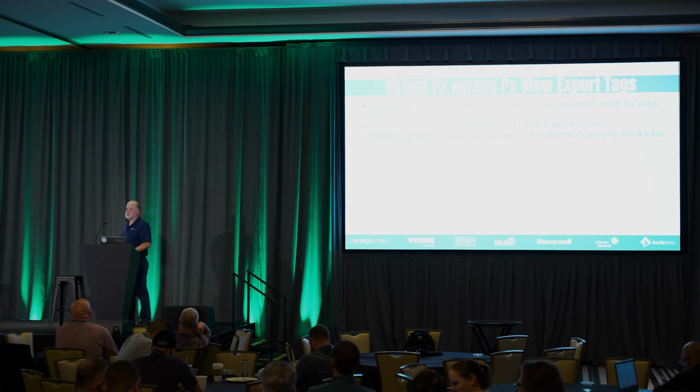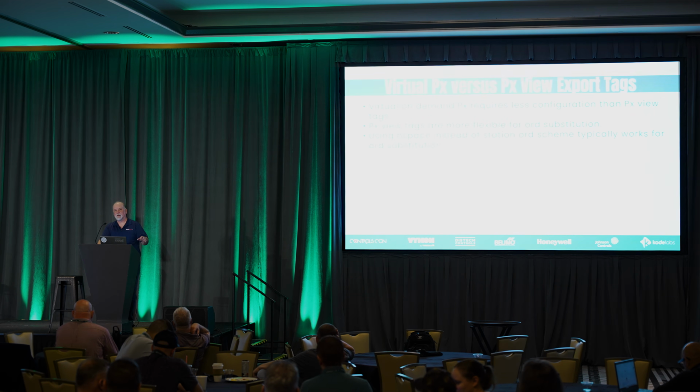How many of you use PXView tags or point tags on jobs? So a bigger percentage of people, that's good to know. If you are doing a server-centric job where you need proxy points, I would certainly say that doing point tags is absolutely the best way to do it, right? It's going to eliminate fat finger errors, it's going to be consistent, the quickest, most efficient way for you to build out those proxy points in the supervisor.